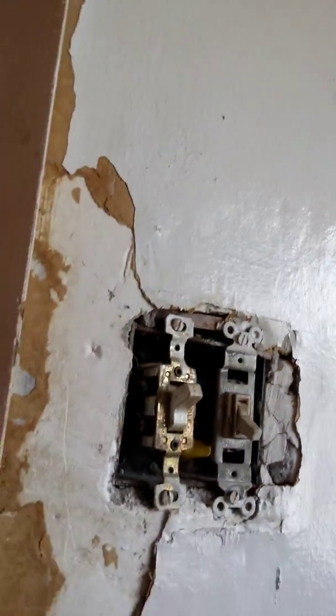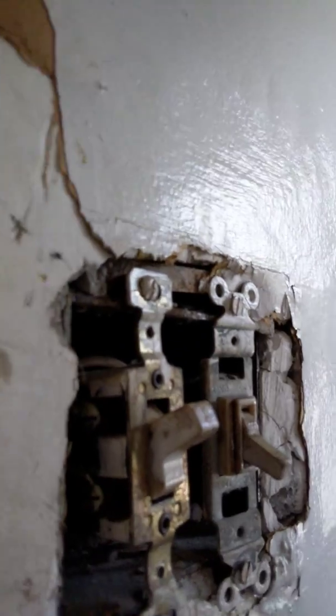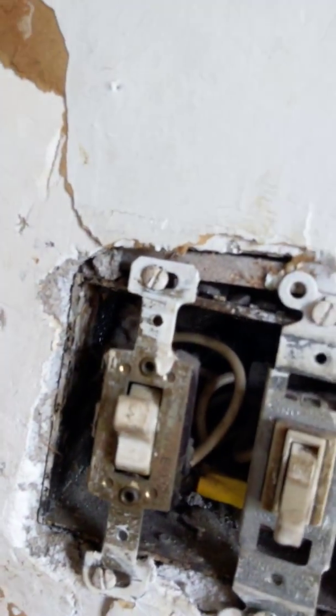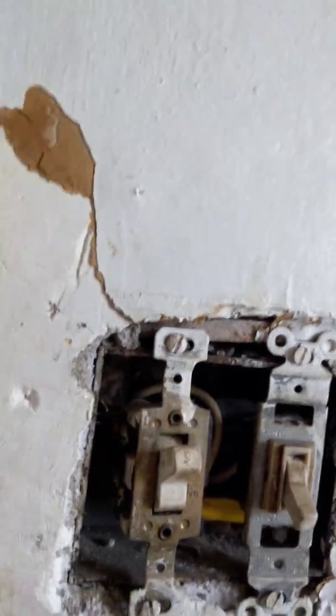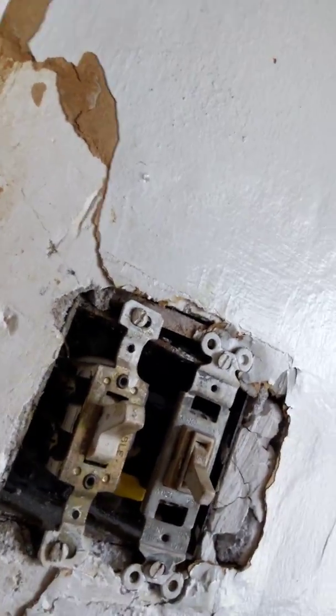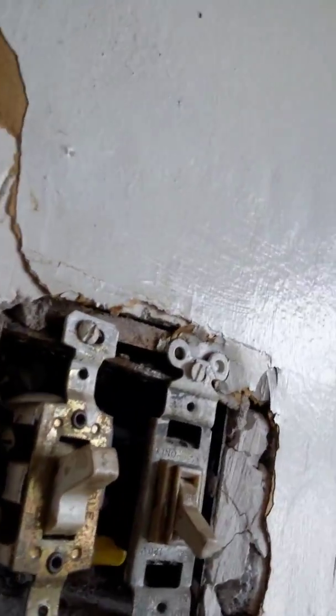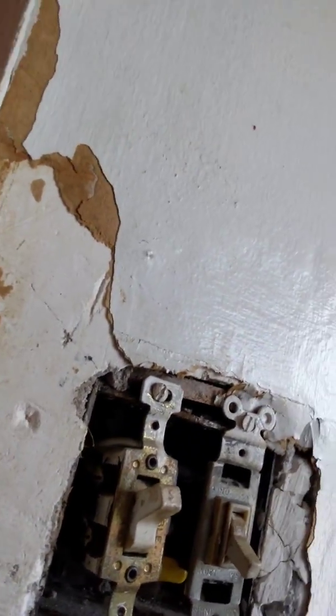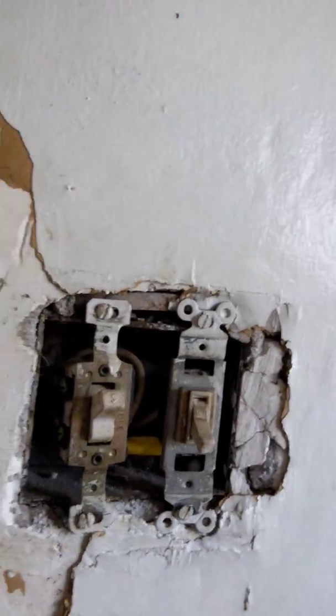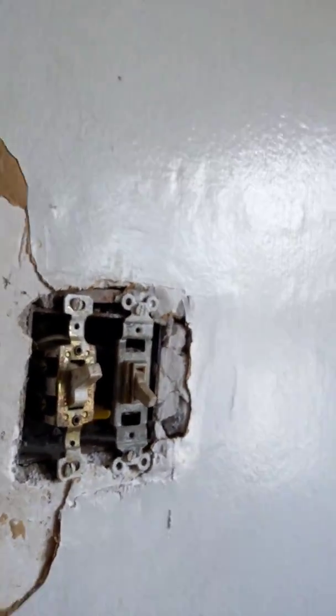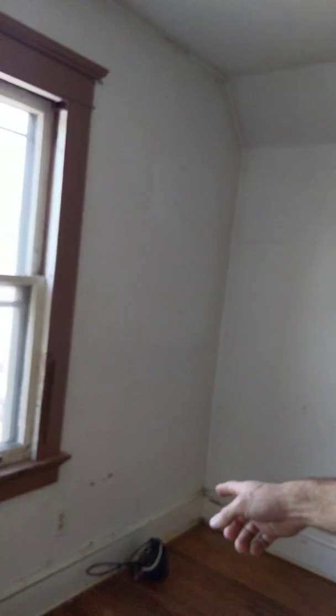Yeah, that's knob and tube. If you take a look in there, these are all exposed - there's two separate cables that run in, one for the hot, one for the neutral. They've got this big insulated shield coming through the metal box for a single cable each. So that tells me the wires are knob and tube, so there's no ground, even though they put the ground outlets in - there's no ground.